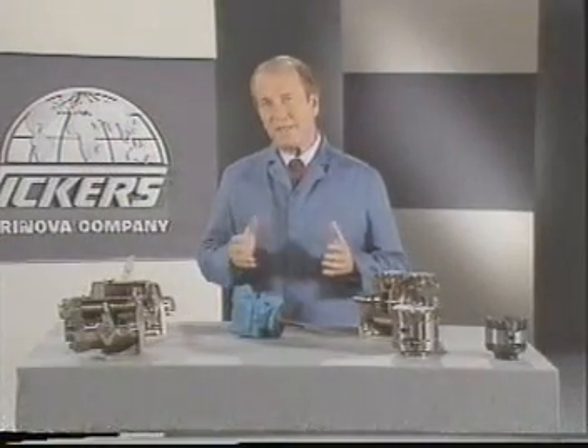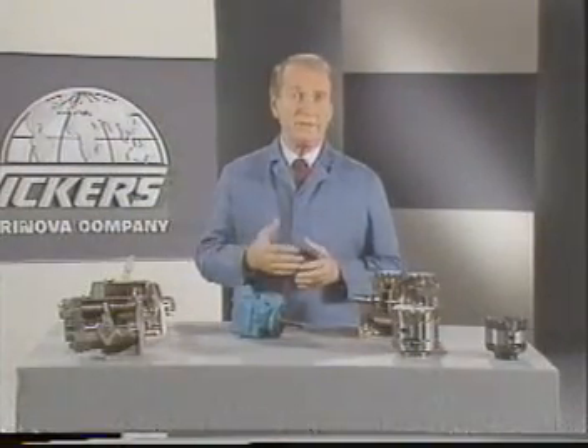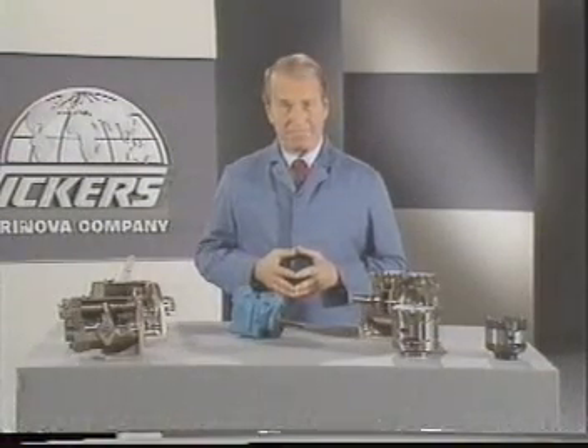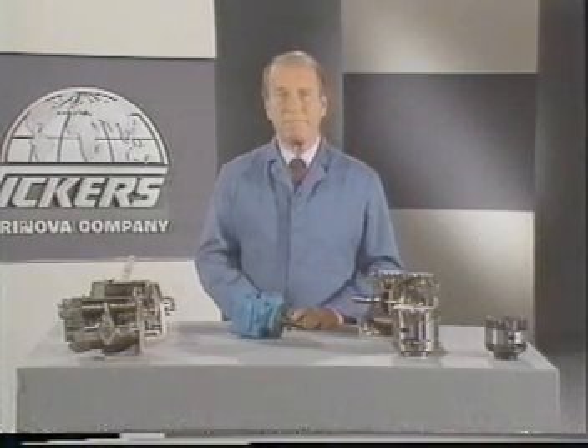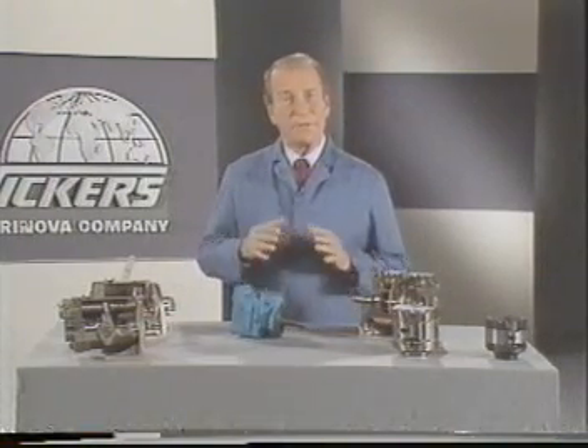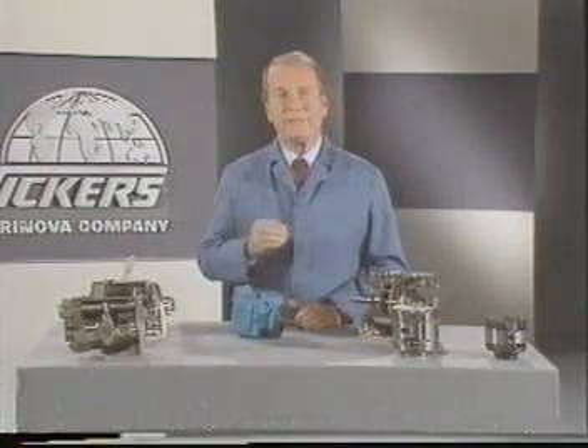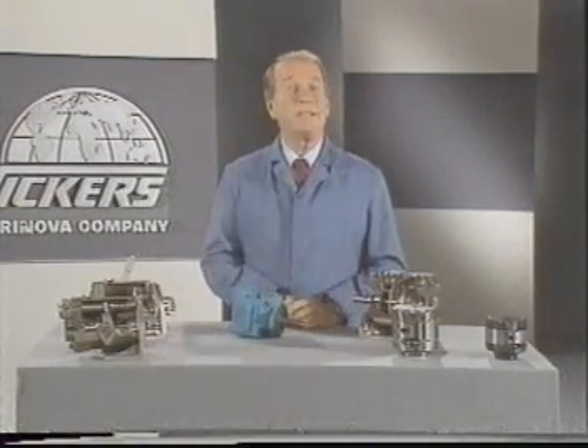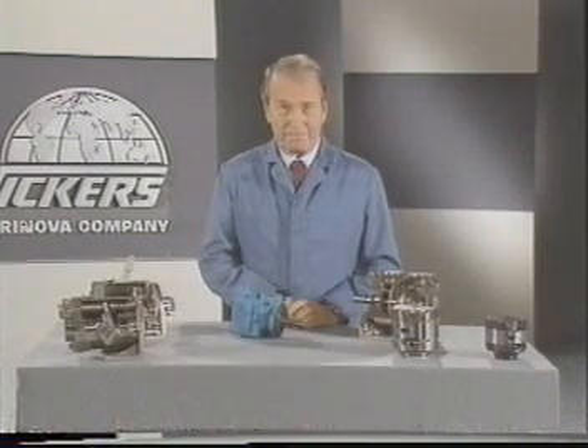Vickers gear pumps range in size from 1 to 50 gallons per minute at 1,200 RPM, although considerably higher drive speeds are permissible. They're available as both single and double units. Other manufacturers have gear pumps that are rated as high as 100 gallons per minute.